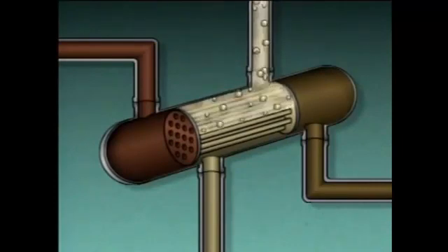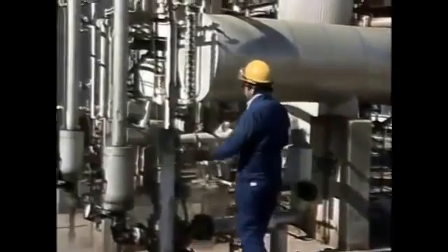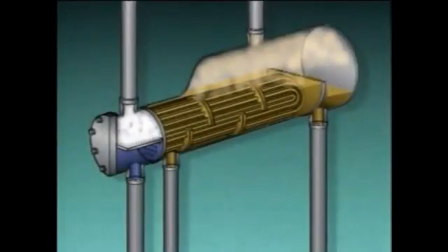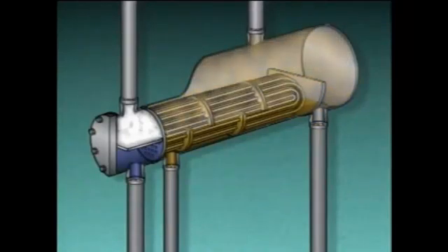As an operator, you may be responsible for the proper operation of reboilers. Like other components in a process, reboilers should be checked periodically to ensure they're operating properly. One important check is the level in the reboiler, made by observing the level in the reboiler's sight glass. The tubes in a reboiler must be covered with the process liquid. If the level drops too low, the tubes could overheat and be damaged.